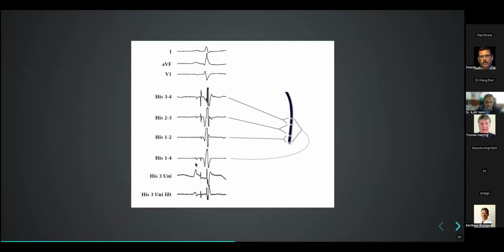So as you keep increasing the inter-electrode distance, a bipolar starts behaving a bit like a unipolar. And you can record a unipolar also, and you can see that you can still see a nice His spike with the unipolar. So this is a unipolar recorded from electrode 3. But you can see in the unipolar that you have good recording of far field activation.